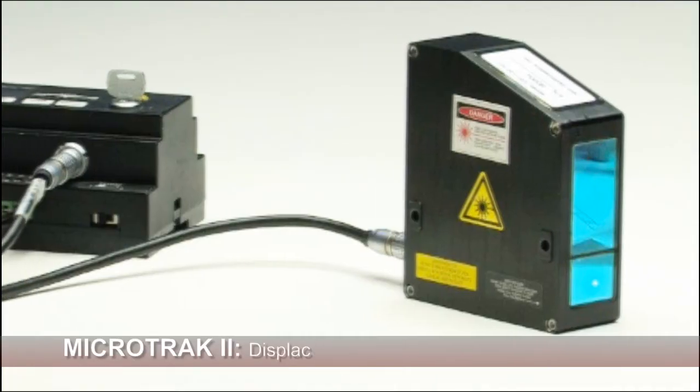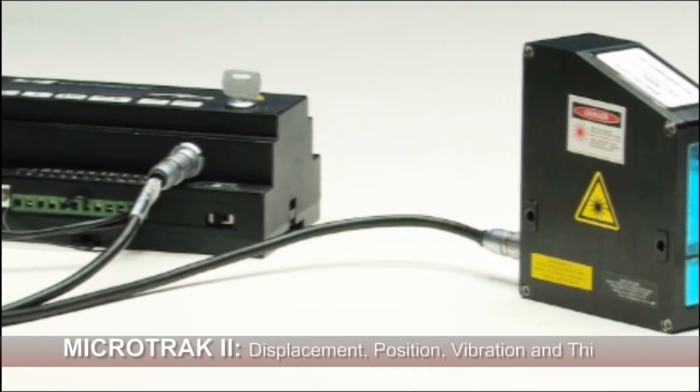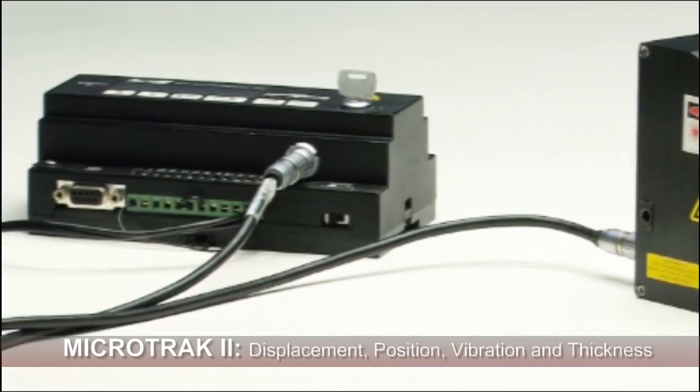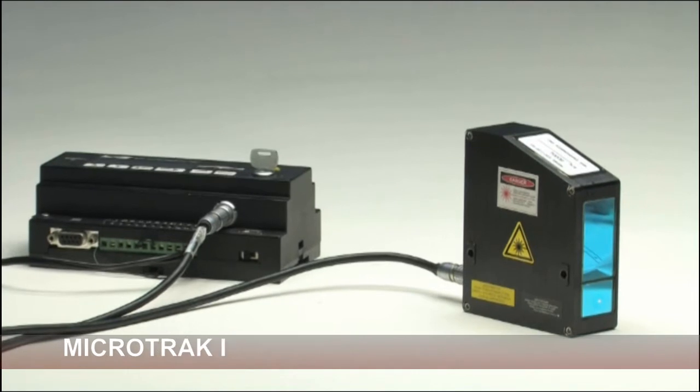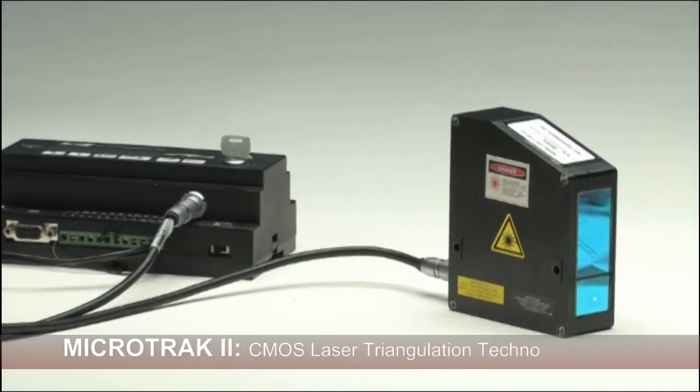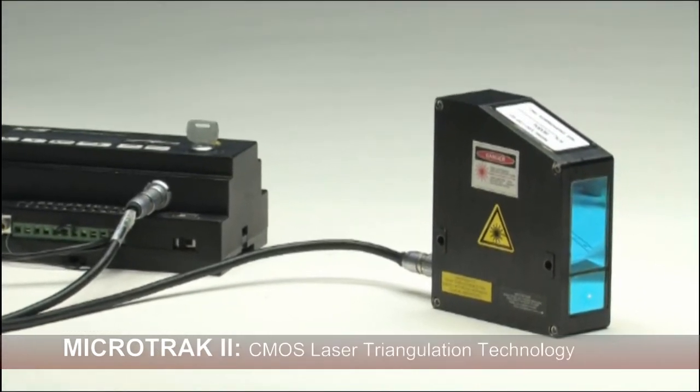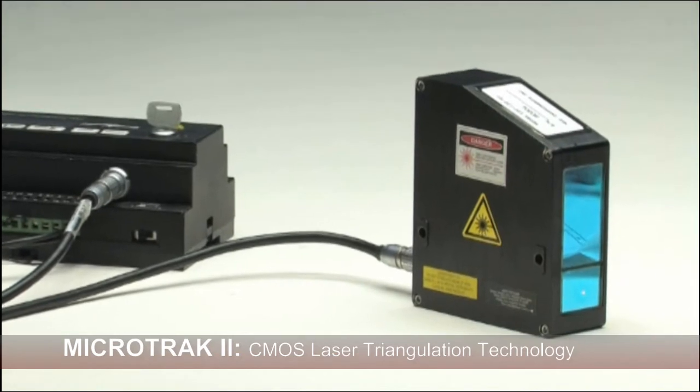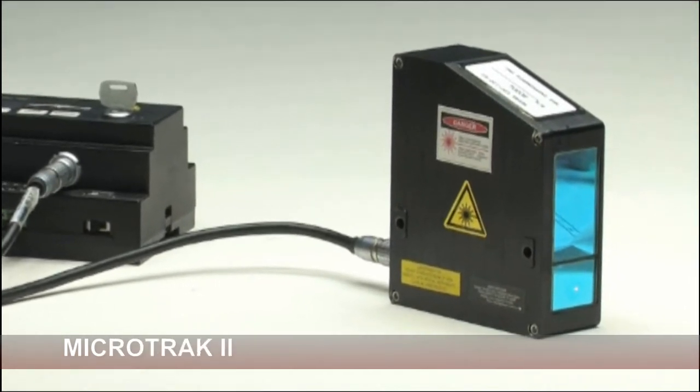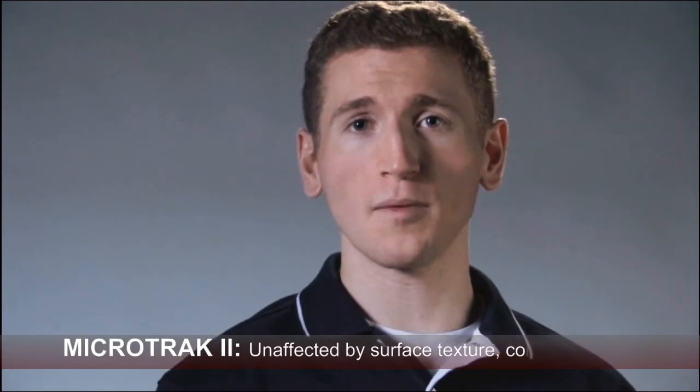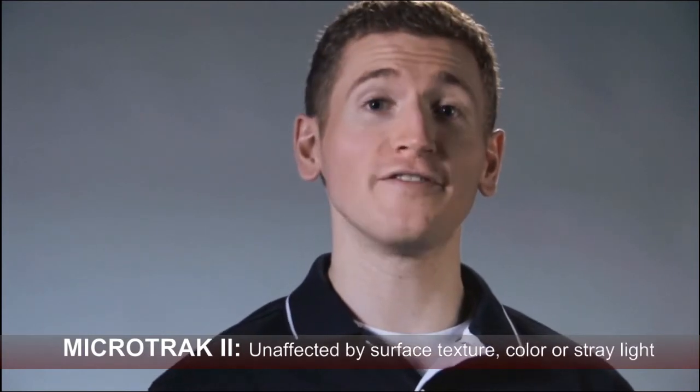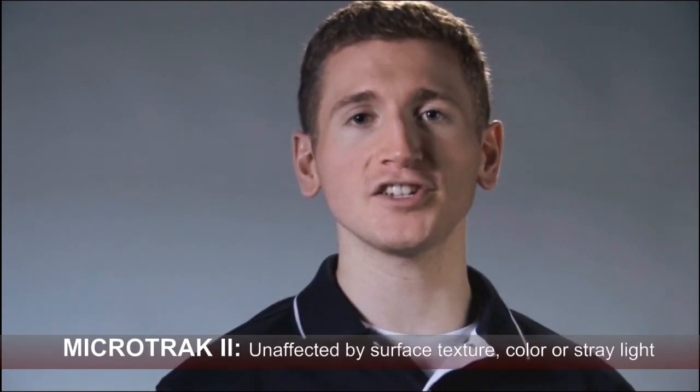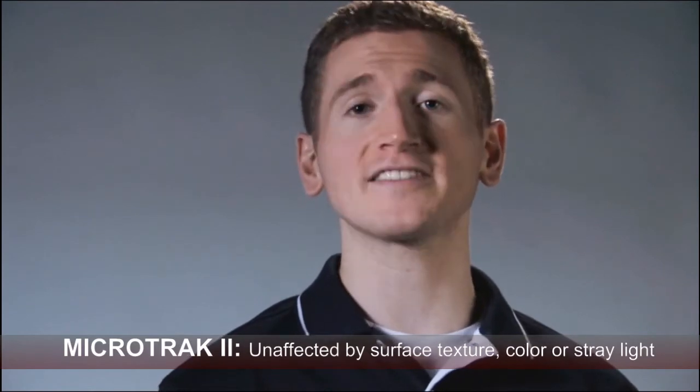The MicroTrak II laser displacement sensor from MTI Instruments operates by emitting a laser beam, which is directed at an object, and then using a CMOS linear detector to monitor the light intensity received on a pixel array. This technology lets you determine spot position more precisely than the older, conventional method of using a position-sensitive detector, or PSD.